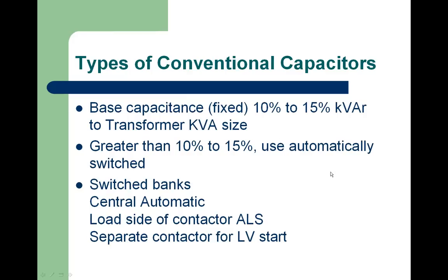of the overall system. In some cases, if we had a 1,000 kVA transformer, and the decision between whether you put in 100 kVAR fixed or 100 kVAR automatic, you probably would be looking at maybe a 2-year payback with a fixed bank, and probably in that size about a 4-year payback with an automatic. So you effectively would be saving the same amount of money. You just would be paying more money for your capacitor bank.